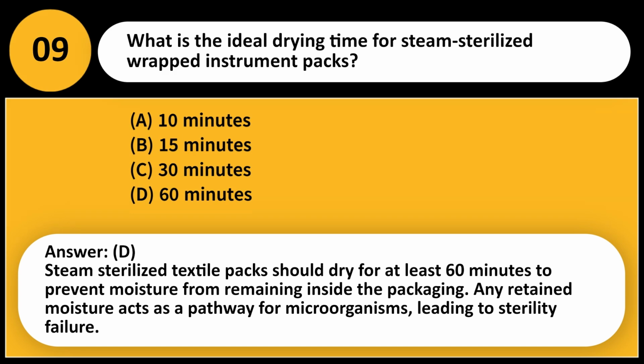Steam-sterilized textile packs should dry for at least 60 minutes to prevent moisture from remaining inside the packaging. Any retained moisture acts as a pathway for microorganisms, leading to sterility failure.